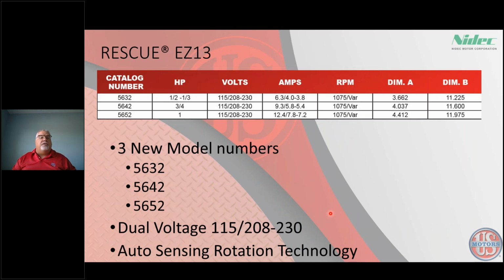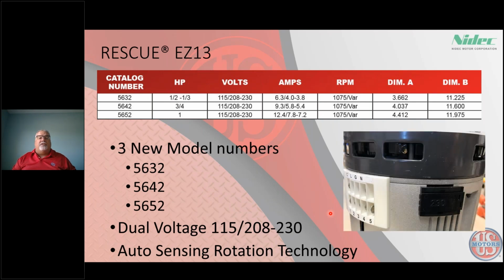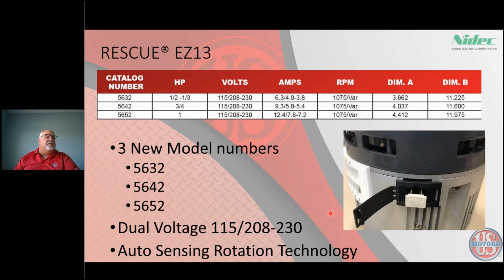They're all dual voltage. So they come out of the box at 208, 230. To change the voltage, it's as simple as opening up this little door and inserting this plastic plug or this junction plug, and then you tear off that black door and you've got a 115-volt motor. If for some reason you need to change it back, it's as simple as just using a little screwdriver to pull that pin out. But it ships 208, 230, because if you hit a 115 with 208, 230, you're going to fry the motor control. So that's why they are that way.